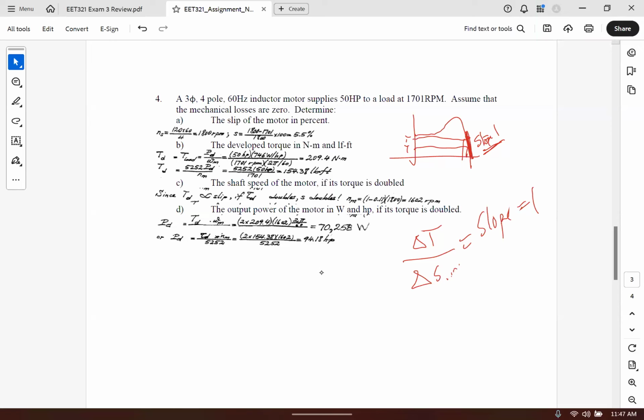If you double the torque, you have to double the slip. Okay, which I get, but for part C, it appeared to me that if you're asking what happens to the shaft speed of the motor when you double the torque, obviously if you double the torque, the shaft slows down. Correct, that's exactly right, and you can see that with this curve—as you increase the torque, you slow down the machine.